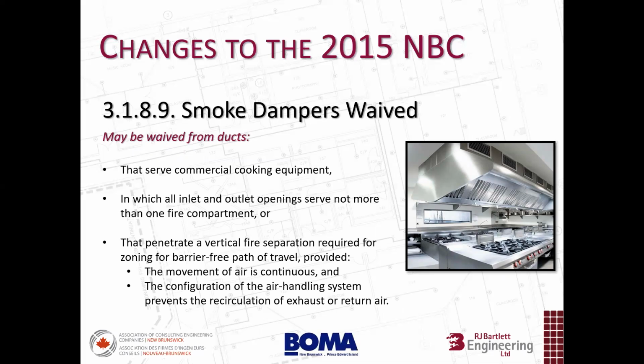Some examples of where smoke dampers are waived: where they serve commercial cooking equipment, obviously smoky environments, or where all inlet and outlet openings serve not more than one fire compartment. An example of this would be if I had a rooftop air handling unit ducted down through a building, down through a couple of floors, and then only provided air or exhausted from that floor, and didn't have any other openings between the roof and that floor level, then we would not need smoke dampers in that ductwork as it penetrates fire separations. If that air handling unit was providing air to multiple floor assemblies, then each of those fire separation penetrations would require smoke dampers.